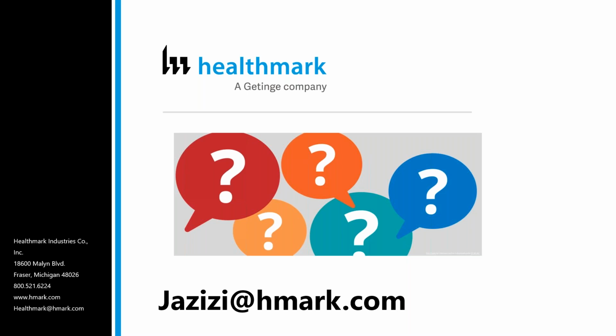Have you got any top tips? Again, make sure that you follow the IFUs, not just for effective cleaning verification, but more so for passing the Joint Commission and CMS, because they are looking at those IFUs. And if you really see something that doesn't exist, bring it up. For example, we found that CMS and the Joint Commission, sometimes if it's not in an IFU, look at the peer-reviewed literature and then make sure that it is being adequately cleaned and processed.